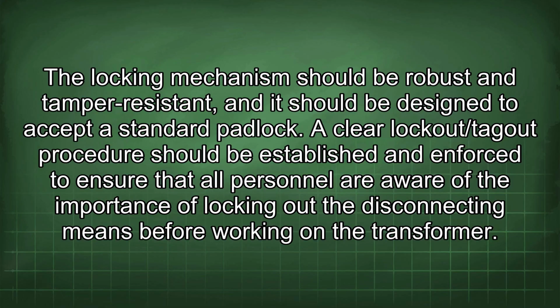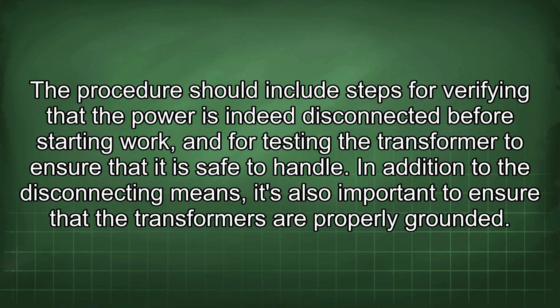A clear lockout/tagout procedure should be established and enforced to ensure that all personnel are aware of the importance of locking out the disconnecting means before working on the transformer. The procedure should include steps for verifying that the power is indeed disconnected before starting work, and for testing the transformer to ensure that it is safe to handle.